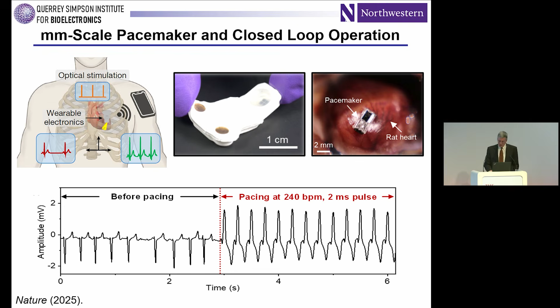It's doing two things. It's measuring electrocardiograms, so we measure heart rate. It has a computational facility in here, so it can compare that measured heart rate to a physician-set threshold. If that heart rate drops below the threshold, then it automatically activates near-infrared LEDs on this side of the device in a pulsatile mode, pulsing that cardiac pacemaker at a rate that increases the heart rate back into a normal, healthy level. So it's operating in a completely closed-loop fashion in a wireless modality. So I'll pass this around as well, so you can take a look at the LEDs and the electrodes for measurement and stimulation. And these are demonstrations on a large animal model.